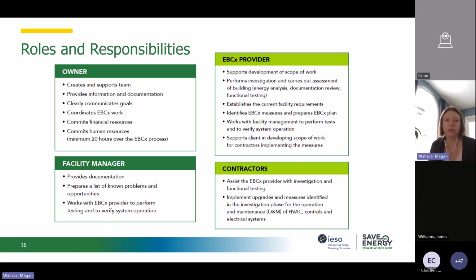Contractors will also be used to assist the EBCx provider during the investigation and functional testing phase, often a BAS contractor or an air and water balancing contractor taking air and water flow readings. Contractors will also be used for the upgrades identified in the EBCx plan.